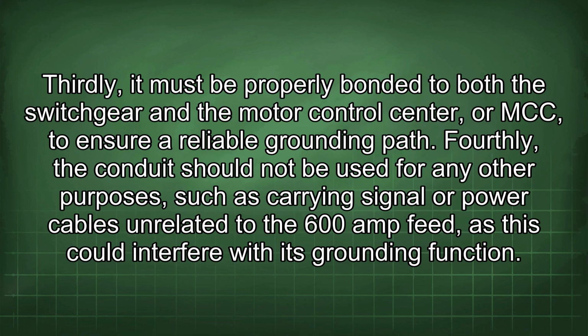Thirdly, it must be properly bonded to both the switchgear and the motor control center, or MCC, to ensure a reliable grounding path. Fourthly, the conduit should not be used for any other purposes, such as carrying signal or power cables unrelated to the 600 amp feed, as this could interfere with its grounding function.